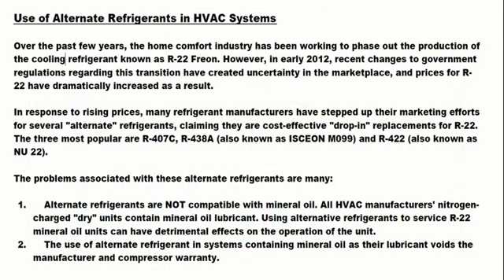Use of alternative refrigerants in HVAC systems. Over the past few years, the home comfort industry has been working to phase out production of the cooling refrigerant known as R22 Freon. In early 2012, changes to government regulation created uncertainty in the marketplace, and prices for R22 dramatically increased as a result. In response, many refrigerant manufacturers stepped up marketing efforts for several alternative refrigerants, claiming they are cost-effective drop-in replacements for R22. The three most popular are R407C, R438A (also known as ISCEON M099), and R422 (also known as Nu22).